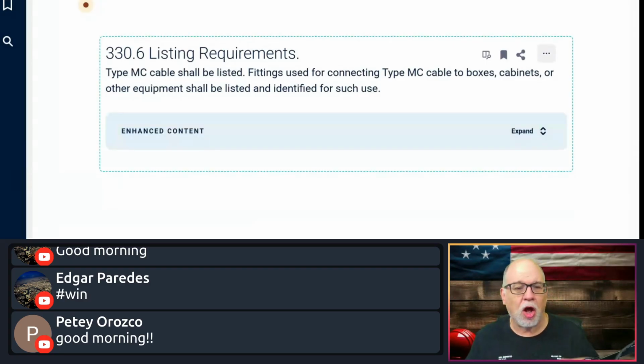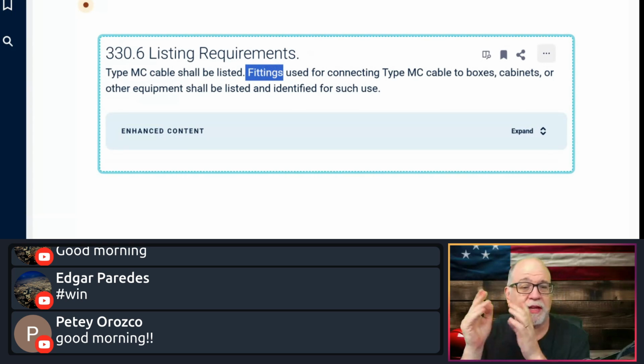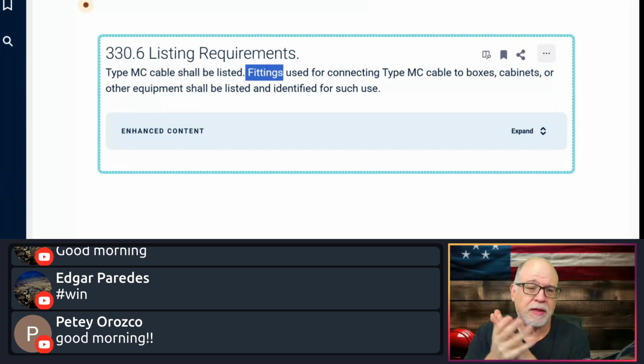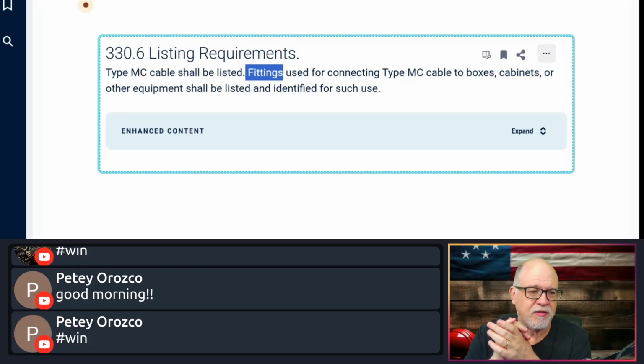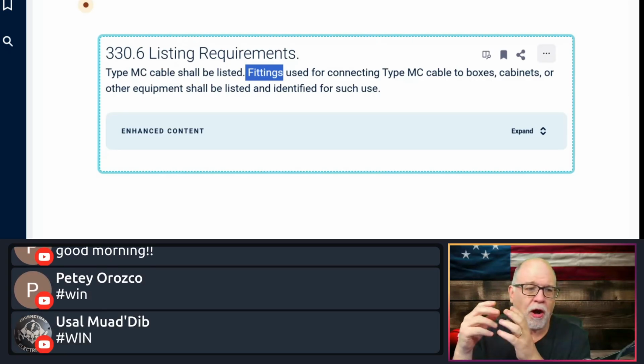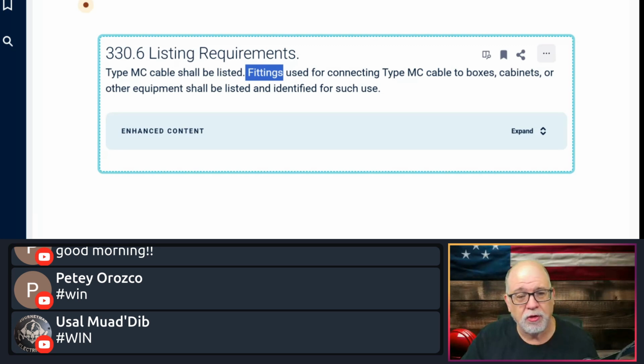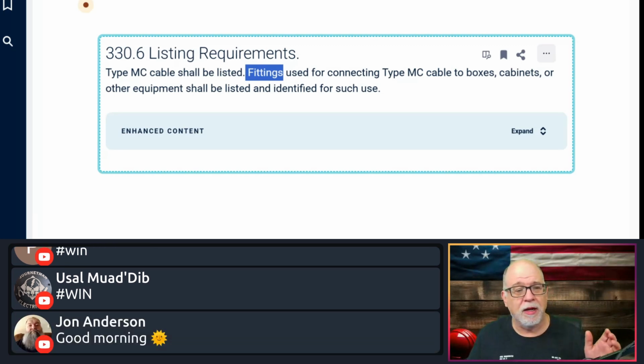Okay. So all of that, by the way, has to be listed. Right. So even the fittings, the connectors. This is where I get people that ask me all the time questions about use of anti-short bushings, right? They say, well, I use them anyway. Well, you can do that if you want, but they're not evaluated that way. They're not evaluated with anti-short bushings on MC. So the fittings that have to be listed for use with MC are evaluated so that there isn't a need for an anti-short bushing, by the way the fitting is actually designed. Now, if it makes you sleep better at night, that's fine. I don't care if you use an anti-short bushing on MC cable. If it makes you feel better, you do you.